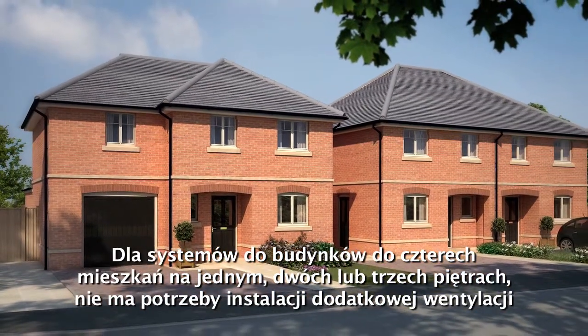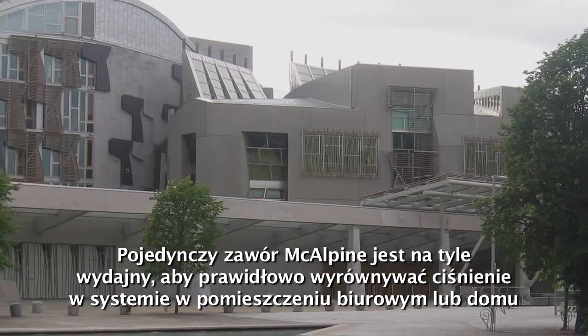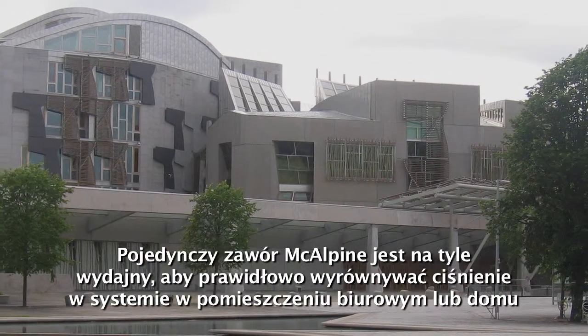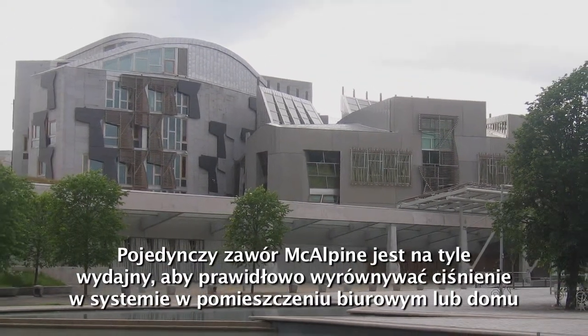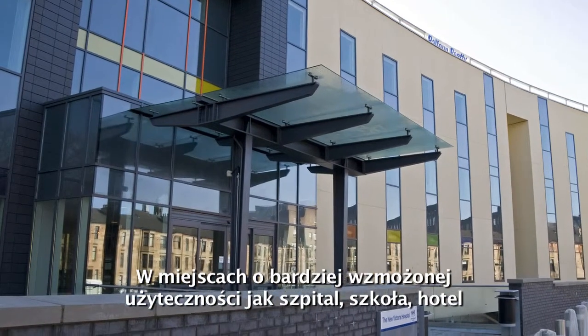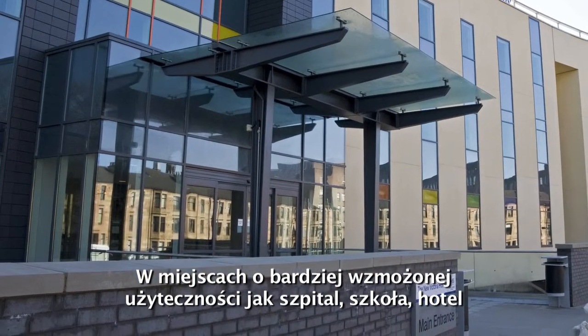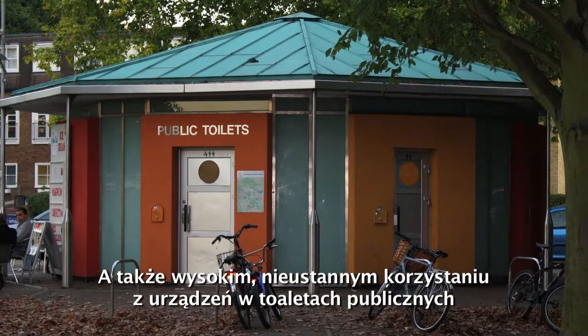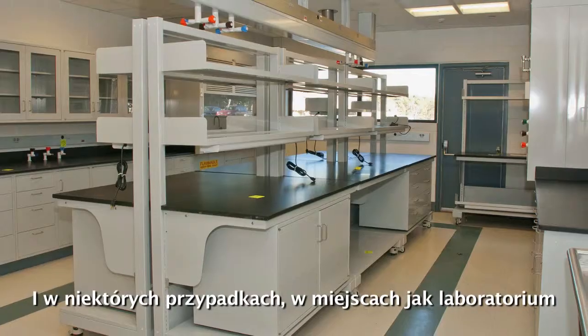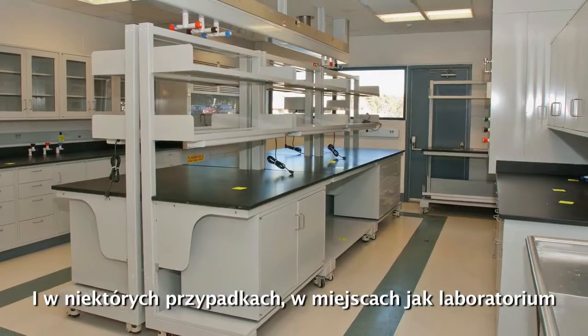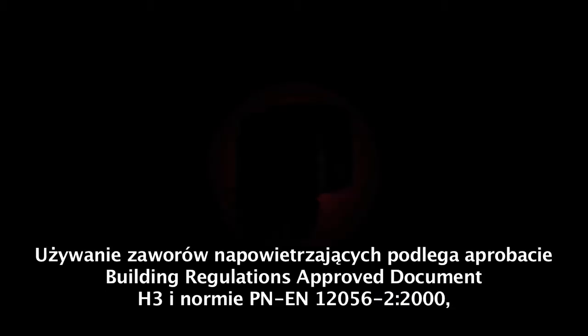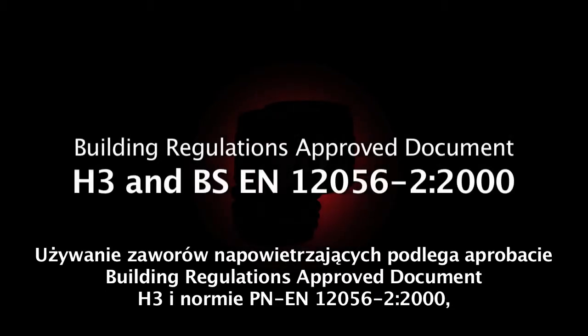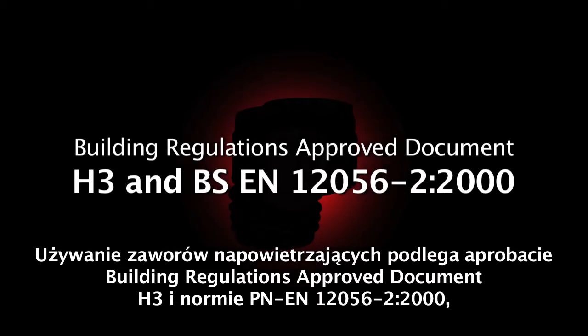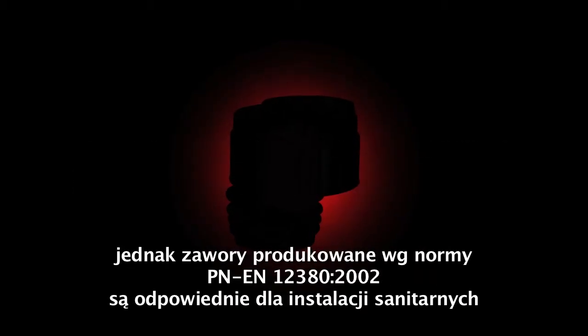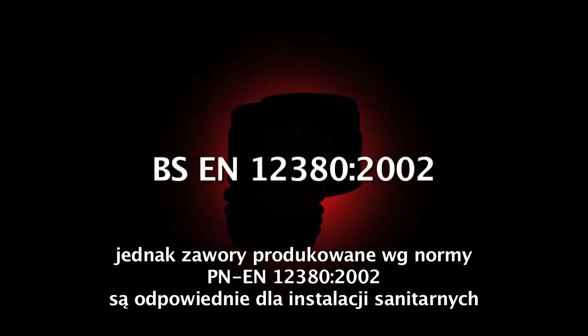A single McAlpine AAV has the capacity to maintain pressure in an intermittent running system, such as a house or office, a frequently running system, such as a hospital, school, or hotel, a continuously running system, such as a public toilet, and in special circumstances, such as a laboratory. The use of AAVs is approved under Building Regulations Approved Document H3 and BS EN 12056, though only AAVs manufactured to BS EN 12380 are suitable for use in sanitary pipework systems.